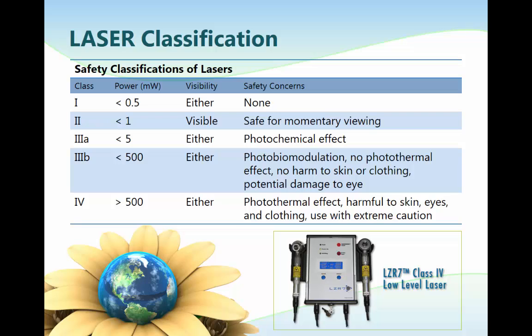The greater the power of the laser, the greater the potential danger. Class 1 lasers have a power of less than 0.5 milliwatts. There are both visible and non-visible laser beams in this class. These lasers are exempt from most control measures, and the laser output is either safe to the human eye or is contained within the device. No special labeling is required for a Class 1 laser.